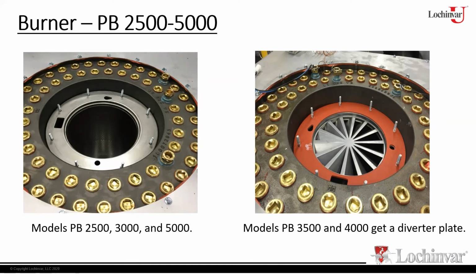Your smaller models, the 2.5 and the 3, and your largest one, the 5, don't get it because based again on the length of the burners, the size of the combustion chamber, we didn't have those combustion issues. We didn't see those problems. It only arose with the 3.5 and the 4, again, just because of the length, the size, things of that nature. So the diverter there helps balance that gas air mixture out in the burner and prevents the noise from occurring. So when you take the burner out, that's kind of pressed in there. I don't believe you can remove that. I don't think that comes out, but for some reason, if it did pop out at that point, make sure it goes back in before you put the fan back on top of it.